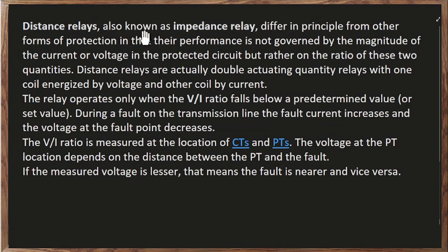Okay, so distance relay, also known as impedance relay, differ in principle from other forms of protection in that their performance is not governed by the magnitude of the current or voltage in the protected circuit, but rather on the ratio of these two quantities. Now, distance relays are actually double actuating quantities relays with one coil energized by the voltage and the other coil energized by the current. So, meaning, yung ating distance relay relies on the impedance, meaning the ratio between our voltage and our current. So, V over I. So, that is impedance.